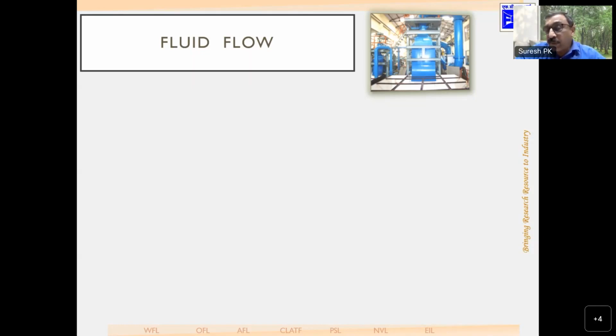So a flow meter which is meant for liquid will measure liquid only. It will not measure liquid and gas. It will not measure gas. If it measures, it will be with some indication which is wrong. So that means you might have seen that for making measurement using turbine flow meters or positive displacement meters, there are air removers kept in that, air eliminators you say. Air is eliminated from the system before you make the measurement. That means the fluid has to be treated properly before you allow it to enter the flow meter and make the measurement. So the fluid flow is important.